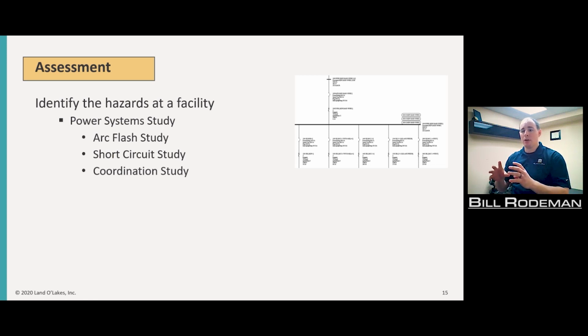But then you can take that and bring it back to compare the amount of current that's actually available to how much your equipment is rated for. What you want is, I have 15,000 amps available to this piece of equipment, and it's rated for 30,000 amps. Okay, your equipment is going to be able to withstand that. What you don't want, and sometimes you'll find, is my equipment is rated for 30,000 amps and I have 50,000 amps available. Well, now, if a fault does occur and you have that 50,000 amps come, the equipment is not rated to handle that. And when we say that, the actual fasteners that hold the equipment together are not able to handle the magnetic forces and everything that comes with that much current, and it's literally going to rip itself apart. So you're able to then identify those and either look at ways to reduce the amount of current or to replace the equipment.